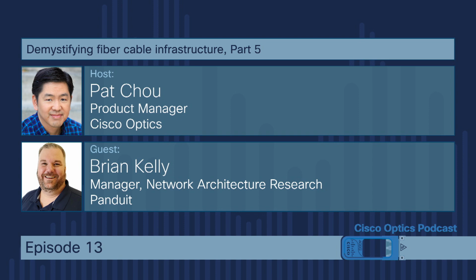There was a lot of work that went into those, because if you don't have enough rack units above and below—some only need space above—but if you don't have enough real estate there, you'll actually starve the switch and kill it faster than you would with just hot air. So we had to do a lot of testing.